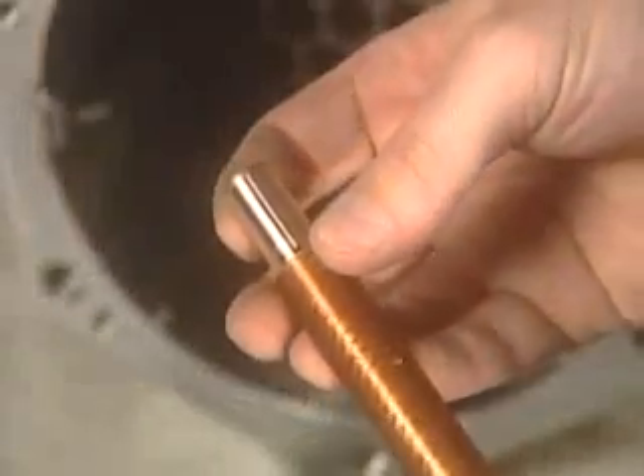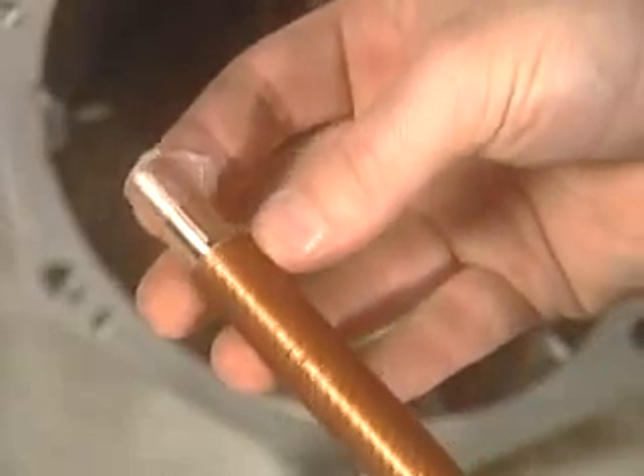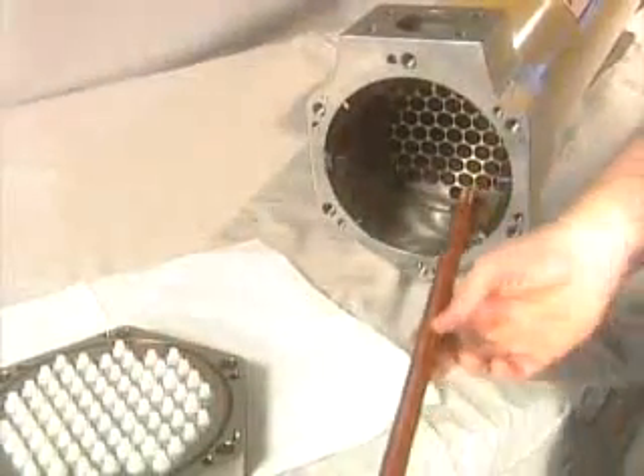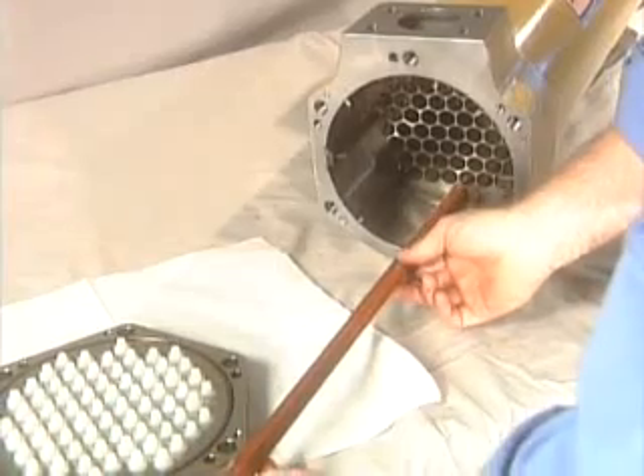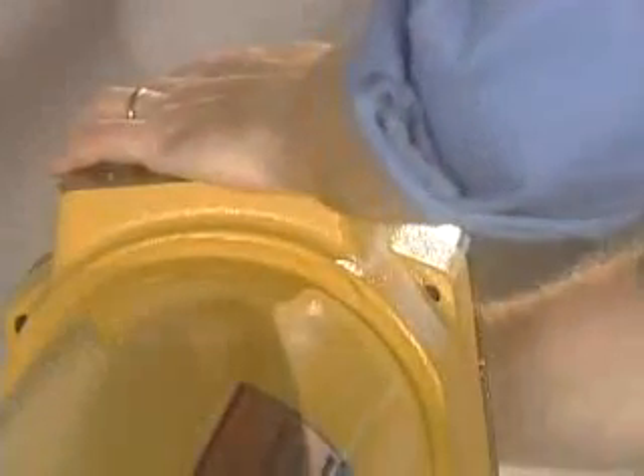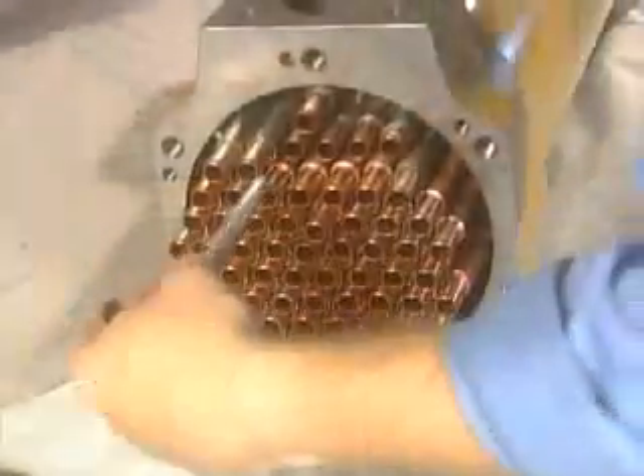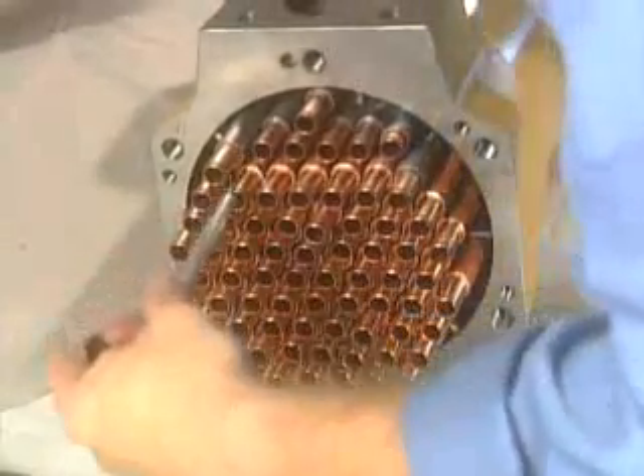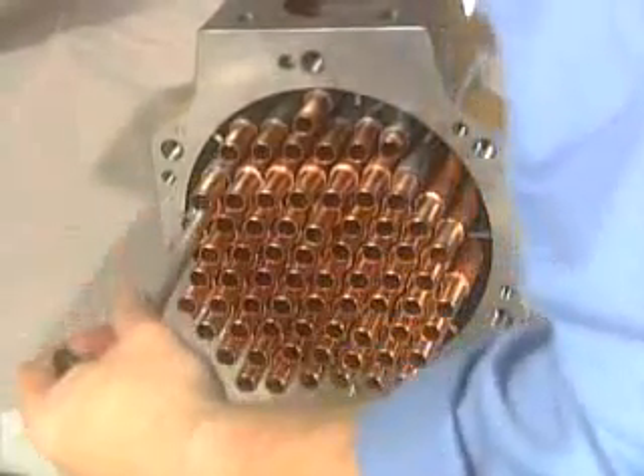Apply a light coat of assembly lube to the clean tube ends. From the open end of the cooler, install the tubes through the baffle assembly and into the attached header plate. Push the tubes through the seals until the tube shoulders bottom out on the header plate. This will push the plastic assembly bullets out of the header plate.